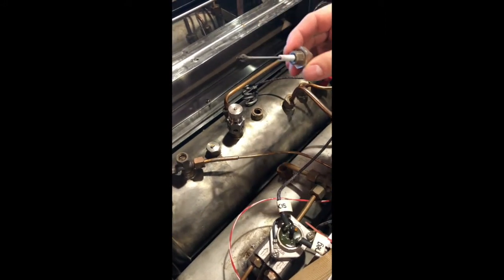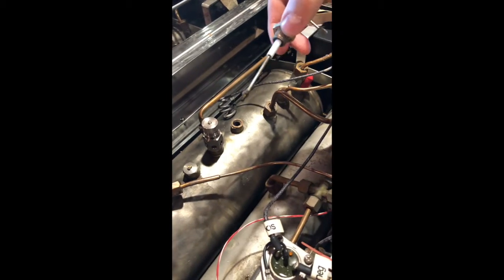So now when this pops off, you can see the buildup right there on the probe—that's the stuff we need to clean off. I'll clean all of this off, get it to look silver and clean again, stick it back in, tighten it down, connect the lead in, and then we'll do a draining procedure, which I'll show you in a second.